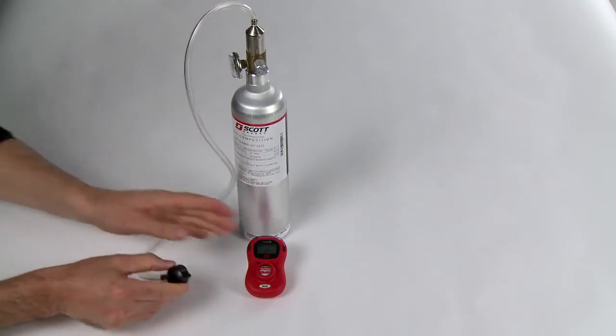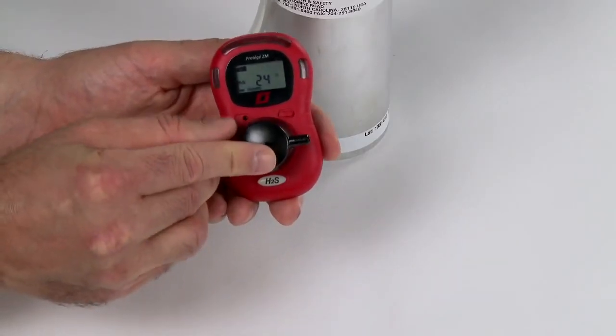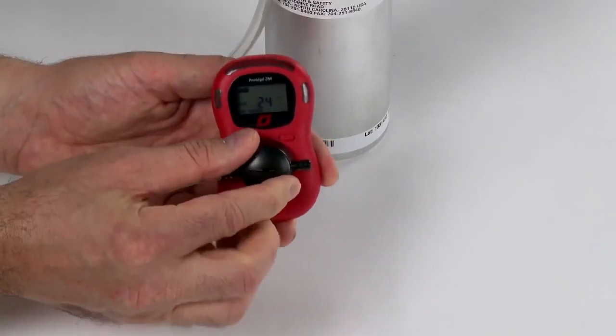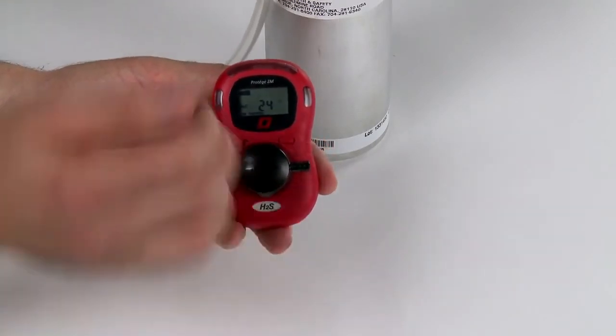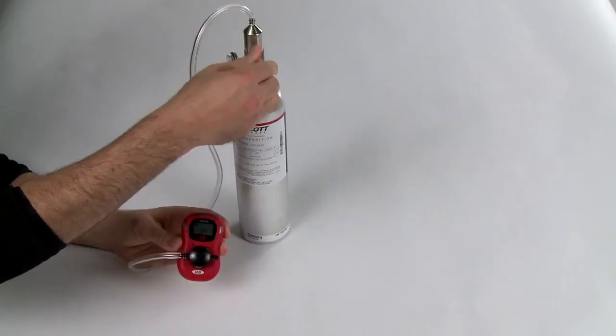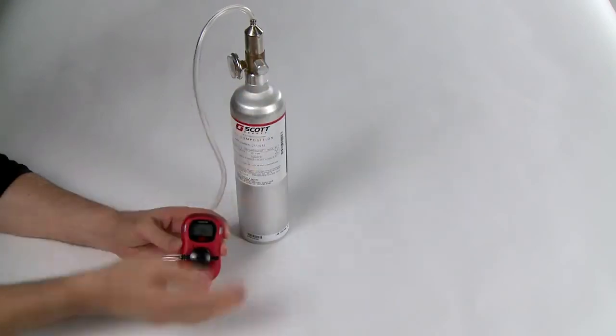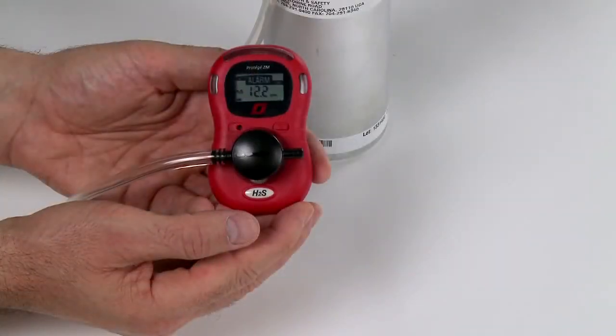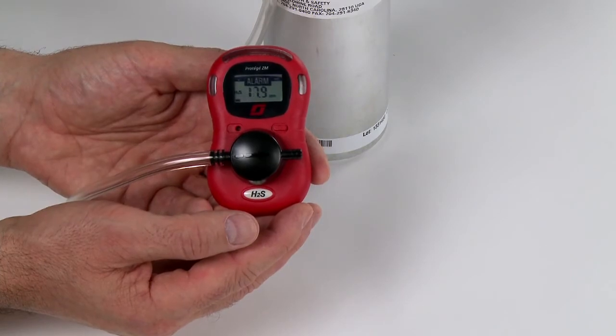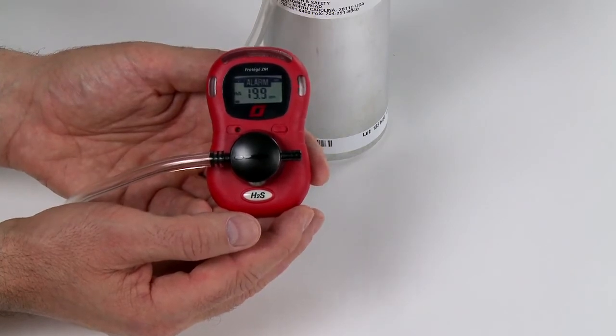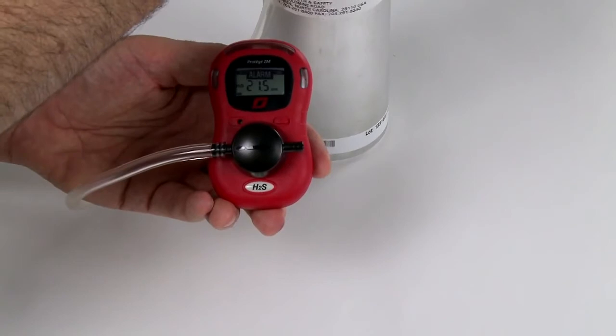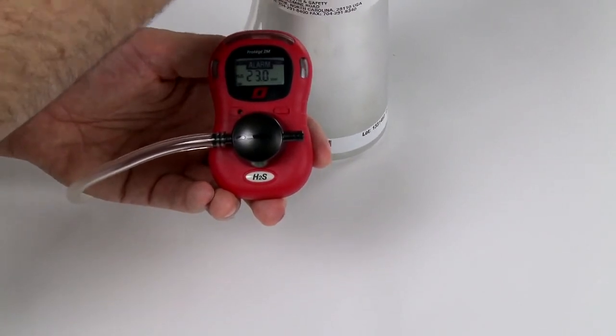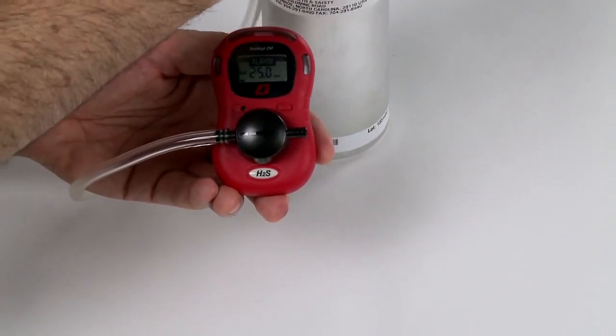Turn on the flow of gas and place the calibration cup over the sensor of the instrument. Wait approximately 30 seconds. The monitor should go into alarm and display the alarm icon on the screen. Vibrate, display the alarm LEDs, and emit an audible alarm. Verify the monitor is working properly and remove the gas.